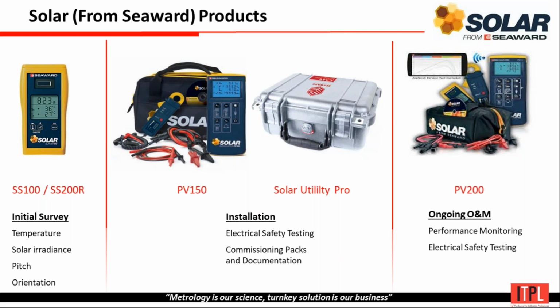So apart from all the PV150 features, PV200 will give us extra parameters like VMPP - voltage at maximum power point, current at maximum power point, peak wattage, fill factor, IV curve, power curve. Then it has inbuilt software, and the software will extrapolate those real-time values to STC value at 1000 watt per meter square and 25 degrees Celsius, and after that we will be able to calculate the degradation factor of a solar panel, how much it has degraded right now.